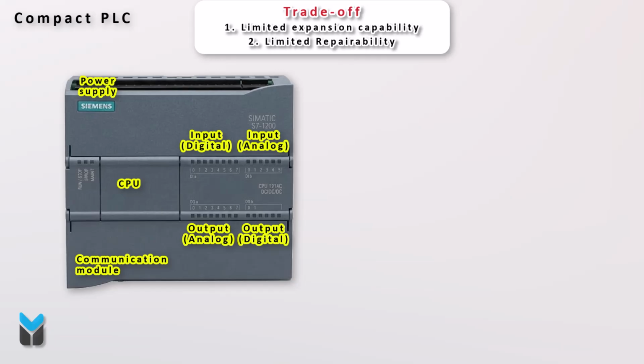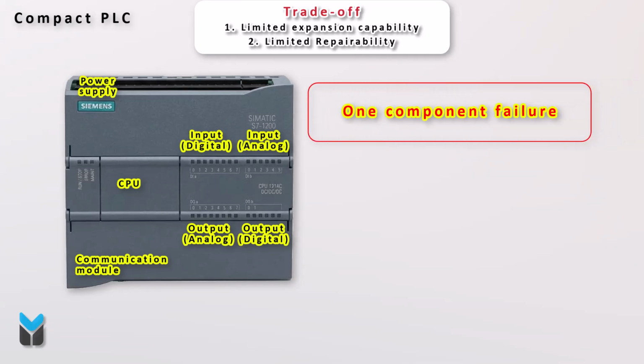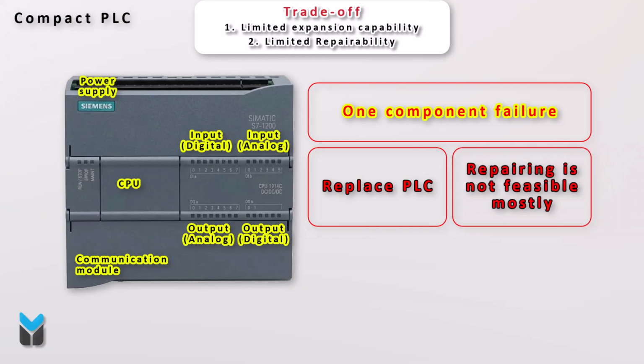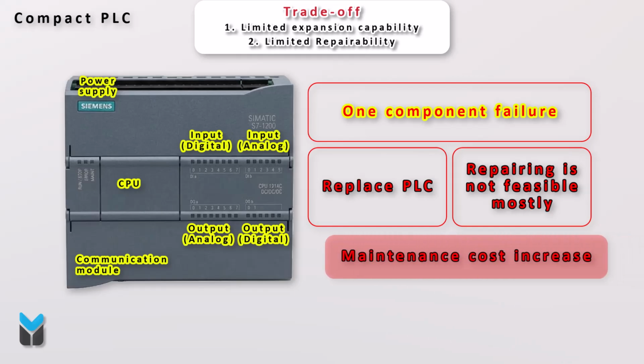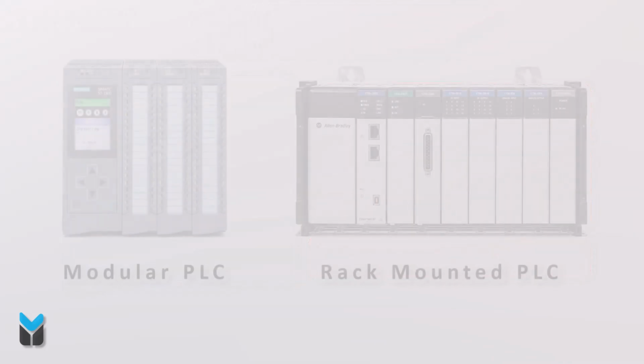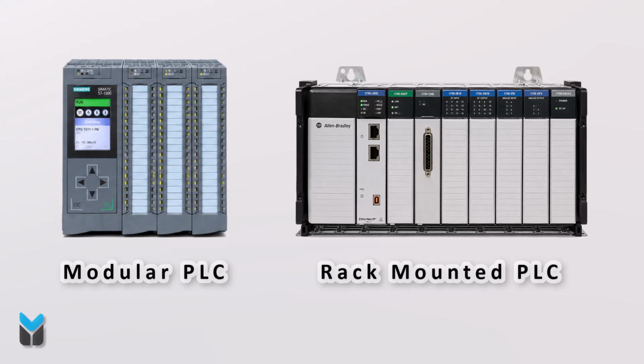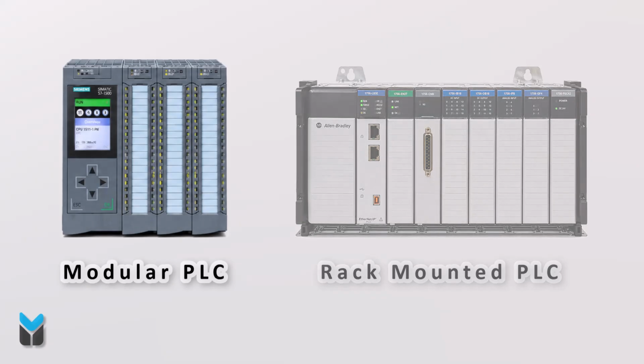Because all the components are built into a single unit, if just one component fails, you may have to replace the entire PLC. In most cases, repairing a compact PLC is either difficult or not feasible, which increases maintenance costs. Due to these drawbacks, engineers often shift to modular PLCs or rack-mounted PLCs for large and complex automation systems.